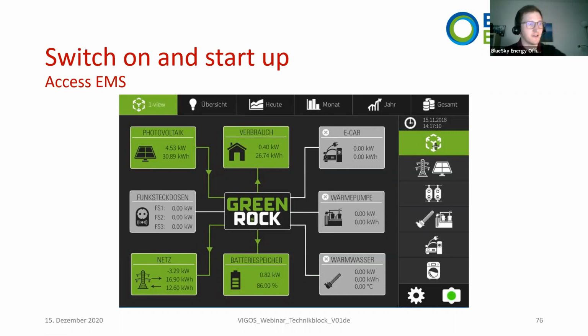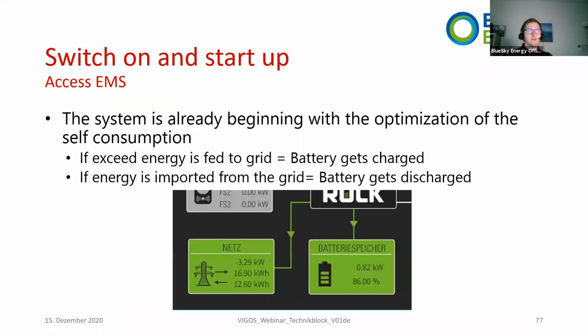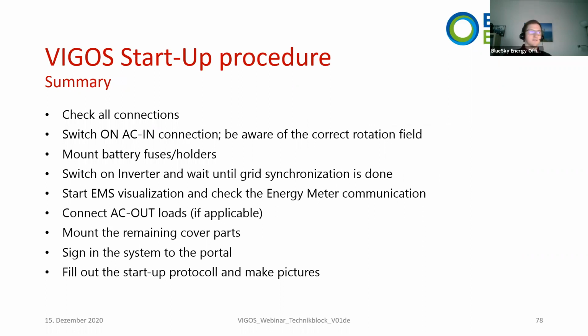So, if the inverter and the grid energy meter are active, the system will already begin with the optimization of the self-consumption. As soon as there would go energy into the grid from the PV, the battery will start charging. And if there would come energy from the grid, the battery starts discharging, so that the grid point stays at 0. So that's the main focus of the system.